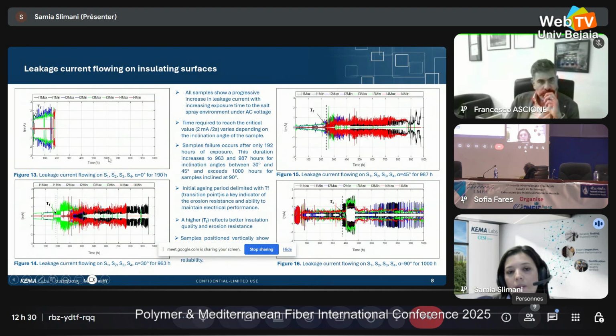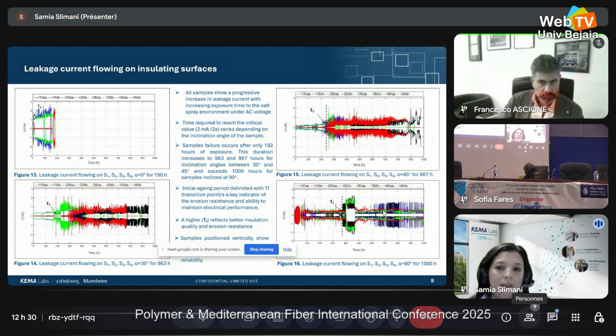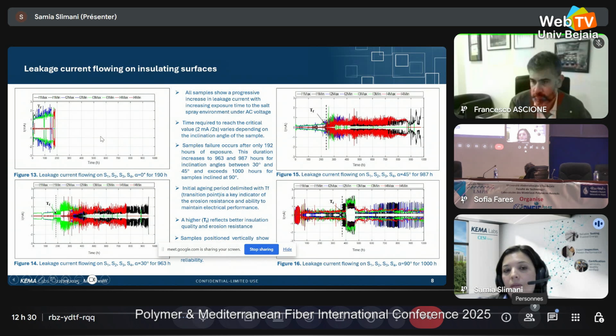For example, when the insulation is in horizontal position, we reached this value only after 192 hours. But for insulation in vertical position, we reached this value after 1,000 hours. So we can say that the insulation in vertical position can resist aging 5 times more than insulation in the horizontal position.